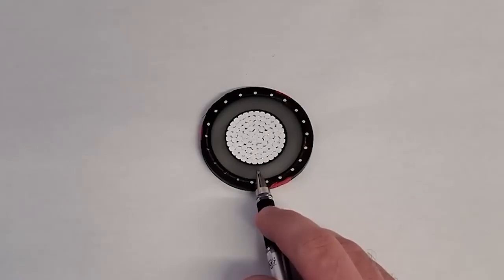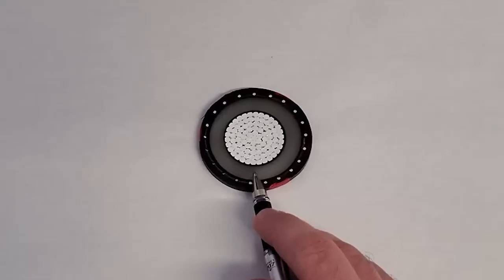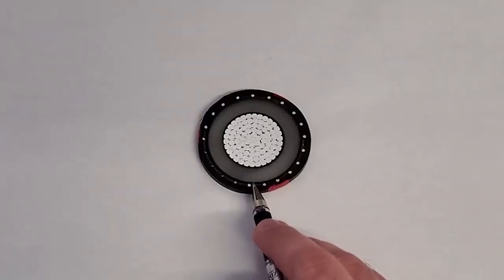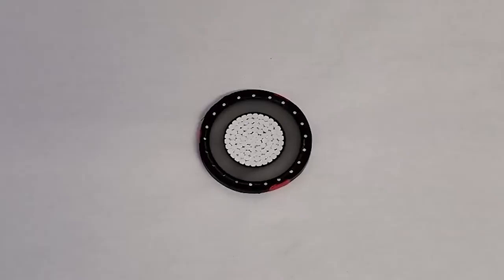But it's only temporary for that 140C. The EPR, on the other hand, is more of a rubber, and it's way easier to install. It's more flexible. It's a little bit more difficult to strip the semicon, which is the next layer. And the EPR is good from -60 to +150, so it does actually have a wider heat range than the XLPE. Plus, the EPR is about 10% higher in cost.